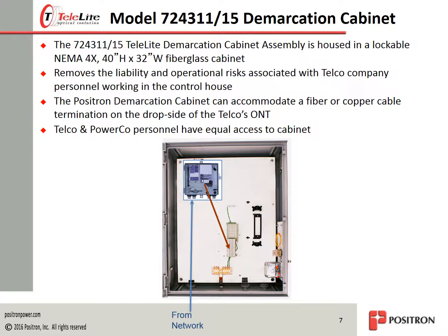From this point, the power company has the option to either install a copper station cable punched down onto the same 66-type protector block that will then feed into the terminating equipment in the substation control house, or the power company may install a TeleLite optical system in the upper right-hand portion of the demarc cabinet and continue with power company-owned dielectric fiber into the control house terminations. This simple and easy-to-manage demarcation facility enables equal access without compromising security inside the substation control house.